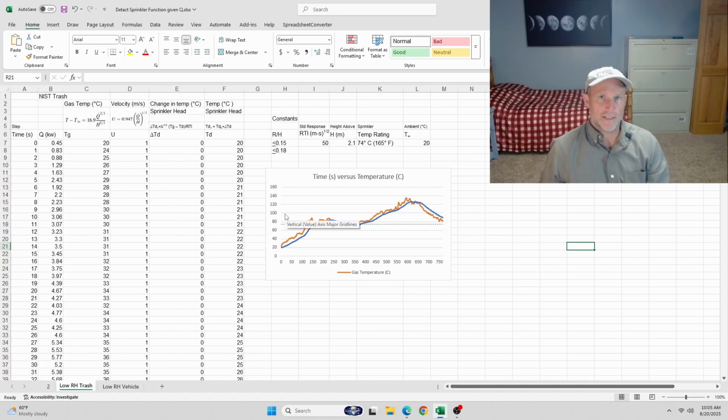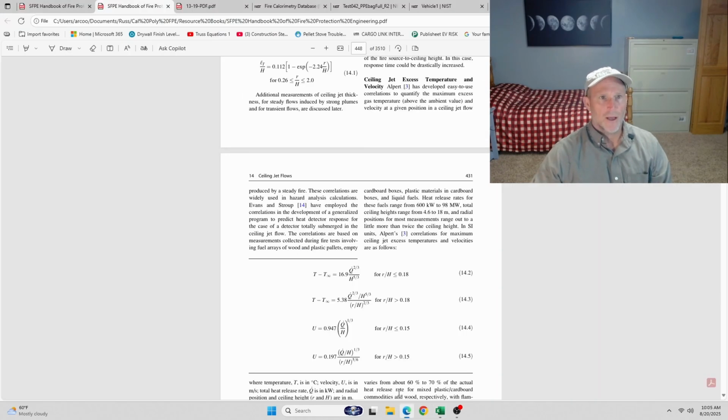So if I had a typical fire, like a trash can fire, for instance, you can actually go and find data that models how much energy is released from a trash can. Generally speaking, it's going to be about 100 kilowatts, and there's some variability there, but I want to show you a source for that information.